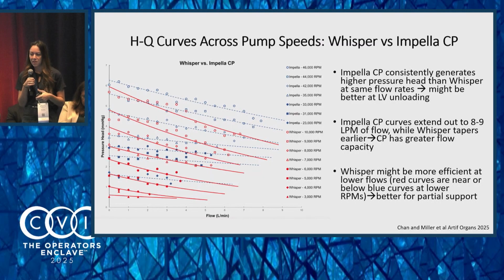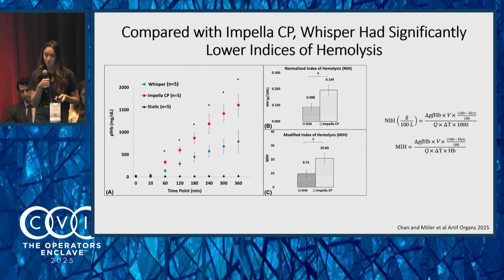The Impella CP consistently generated a higher pressure head than the Whisper at the same flow rate, so it might be better at higher levels of unloading, which is as it's designed. On the Impella CP curves, you can see it extends all the way out to 8 to 9 liters per minute of flow, but the Whisper tapers earlier - meaning the CP has a greater flow capacity, something we could have already predicted. But the Whisper might be more efficient at lower flows - you can see the red Whisper curves are near or below the blue curves at lower RPMs, so it might be better for partial support. At least that's what I'm gleaning from these HQ curves.